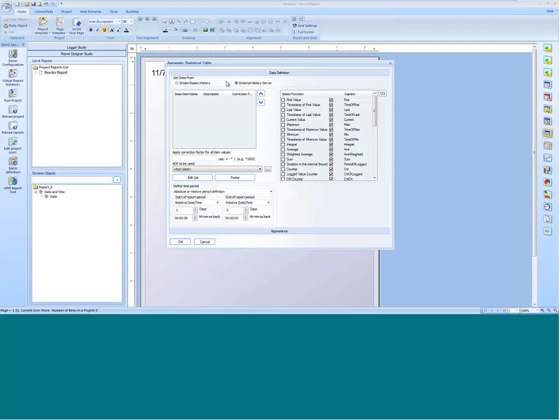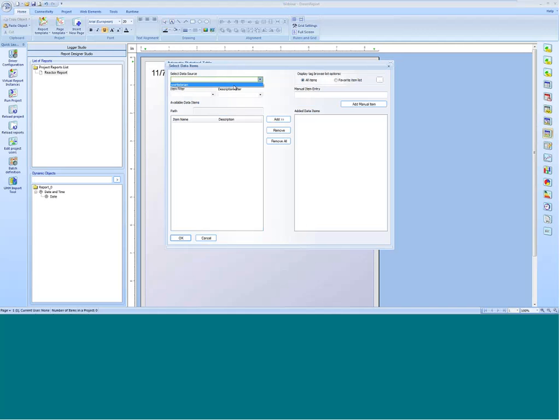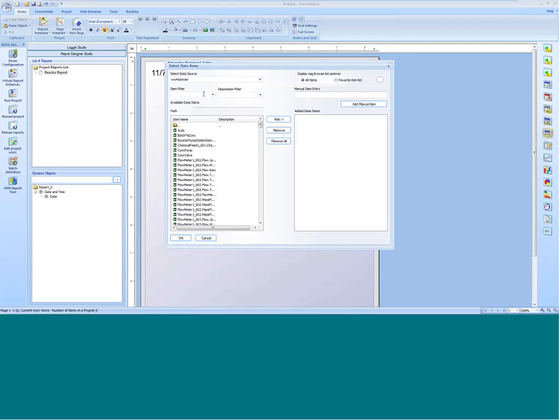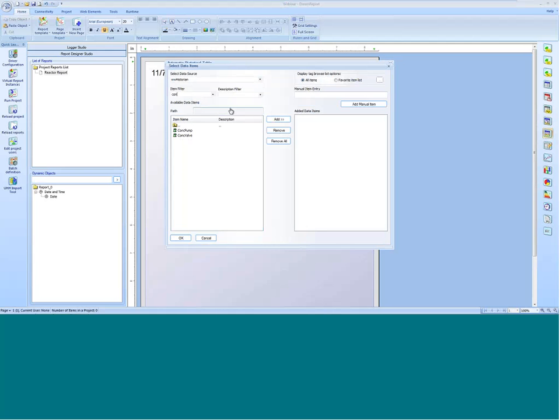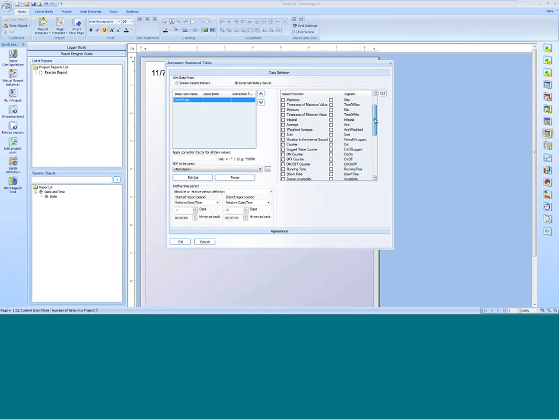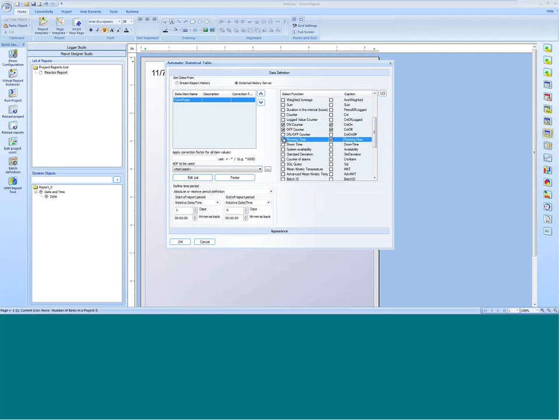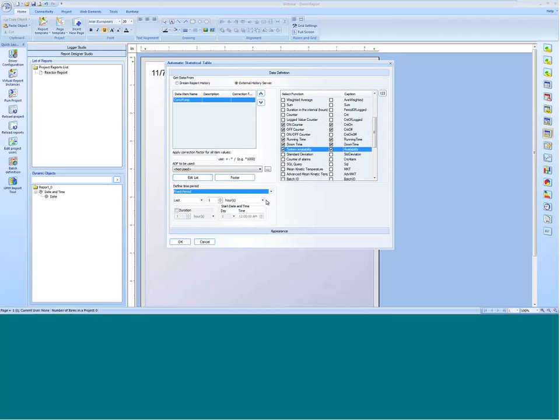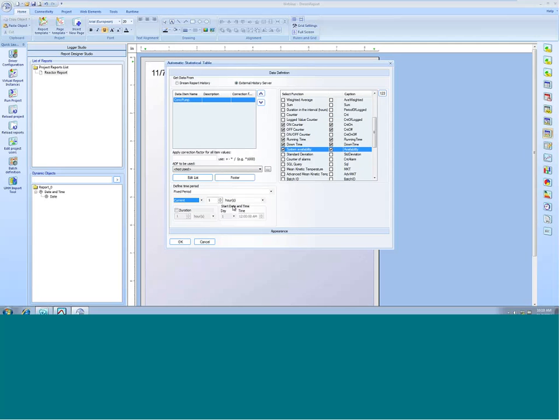I'll select External History Server because my Wonderware Historian is an external history server, then click Edit List. My data source is my Wonderware Historian, and I can browse to a specific tag. I'm going to use my pump to look at the uptime/downtime for that pump. I'll click Add and OK. Here are some statistical functions out of the box — I want to see how many times the pump turned on, how many times it turned off, the running time, the downtime, and the system availability — which is the percentage of time it was running. For the time period, I'll pick a fixed period and look at the current hour.